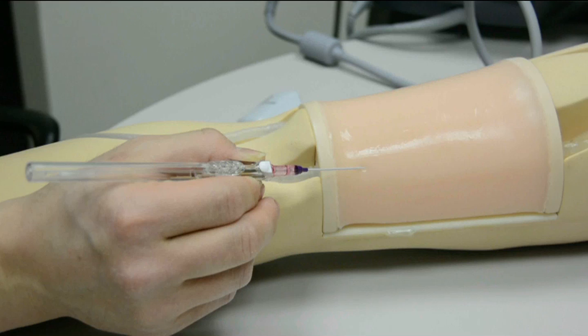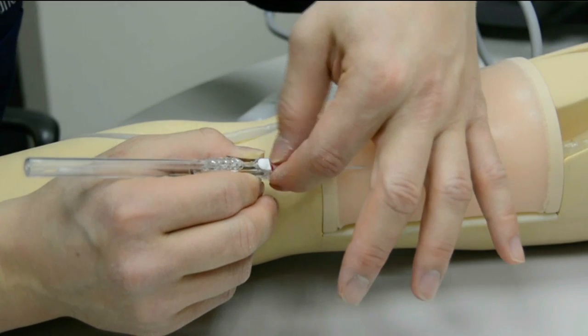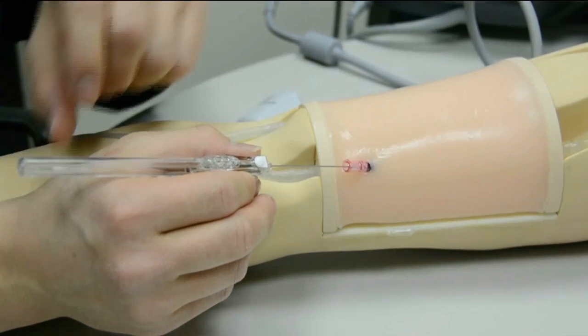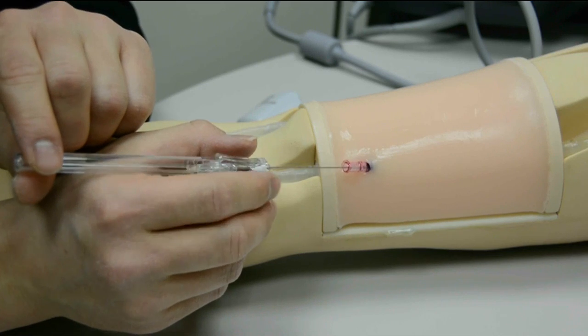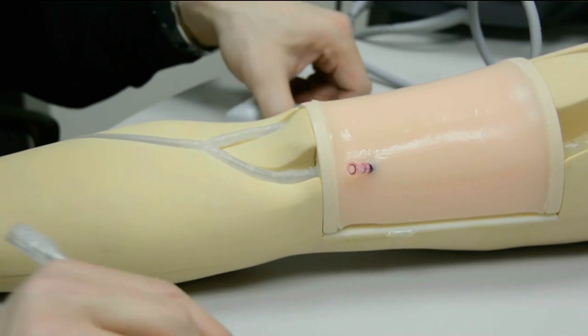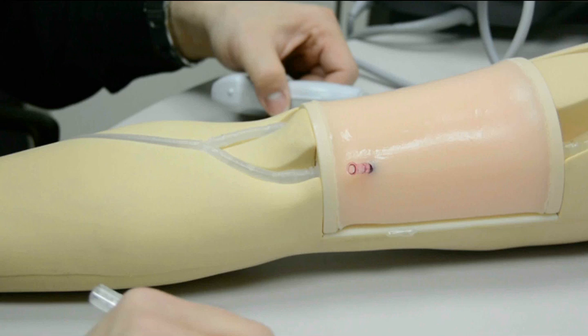Once your wire has been extended and confirmed within the vessel, slide the catheter over the needle and the wire into the vessel to the depth you need — full depth. Then press the actuation button to retract your needle. You can then remove the wire at that point. In the demonstration we rotate the needle, but you don't have to do that — it's purely so that the hands are not in the way as we activate the actuation button.